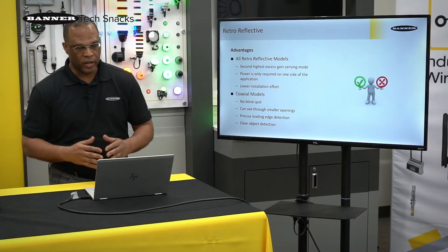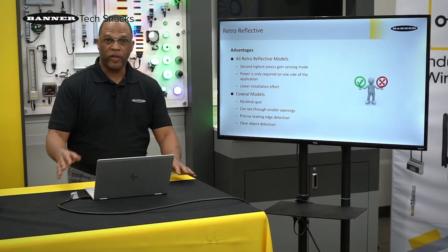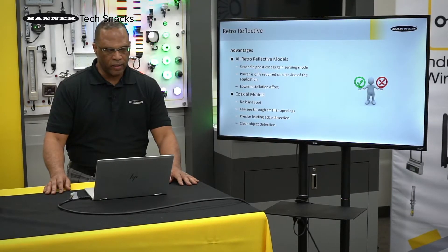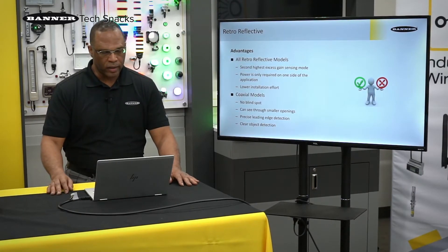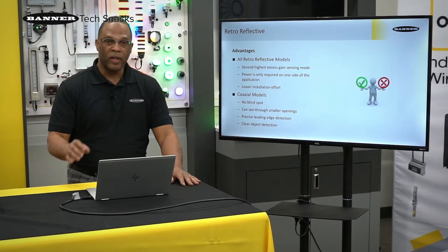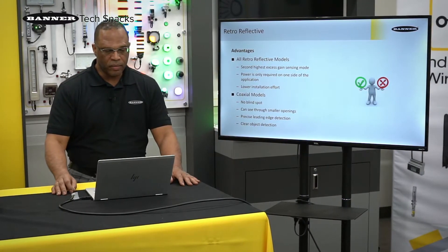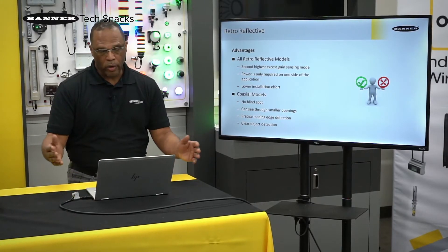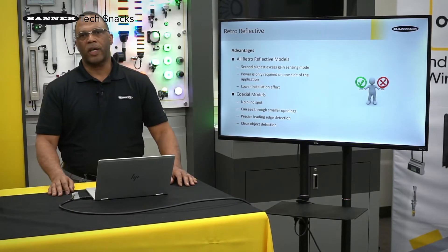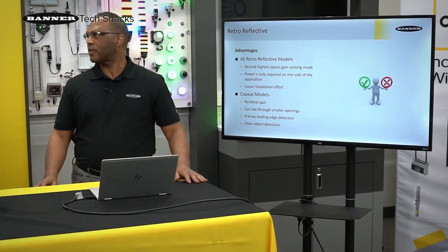Wrapping it up, the pros of retro-reflective: it offers the second highest mode of excess gain, you only have to power up one side, there's no blind spot if you use a coaxial sensor, it also gives you a very tight beam to see through small openings or for precise leading-edge detection, and we can detect clear objects.